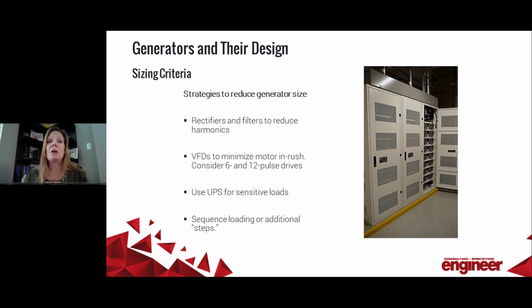And as I mentioned before, harmonics and load transients are big issues that must be dealt with. One way to deal with the harmonics is to provide filters and rectifiers on nonlinear loads. You could include VFDs or soft start motors, which could assist in the overall voltage dip that I talked about, because those will drastically reduce the starting current on some of those larger motors. And then further enhancements would be to consider 6 and 12 pulse drives that will help to mitigate that voltage distortion.